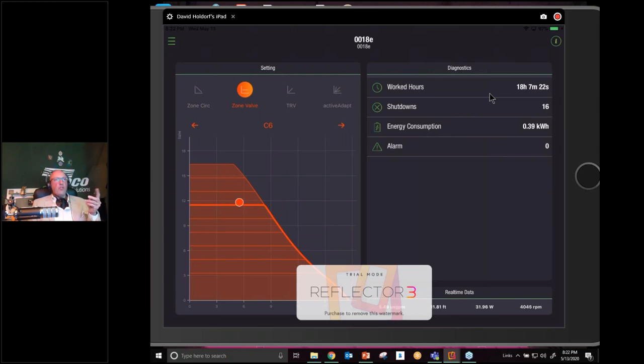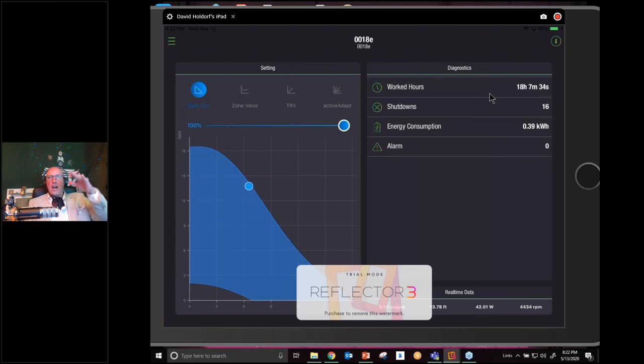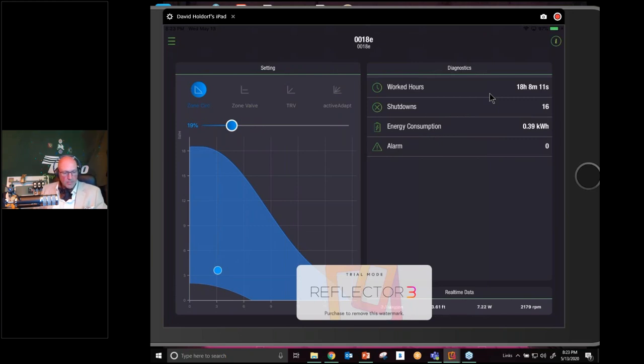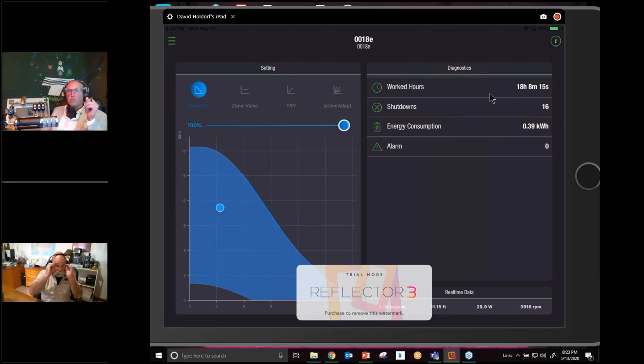One of the questions was, why did the dot flash red briefly? It was probably under the zone circ when I was speeding it up and down and changing it quickly. That just means it was finding which curve to operate on. So it just took a while to learn. I just went from 100% down to 37, and the dot was hunting all over the screen. Usually when I start low and go to high, I see it go to red, or when I've got low flow on the system. Right now I've got all three zones open. I find it's on the low flow when I get down to that 10% range and then crank it up, and it's closer to the left side of the curve compared to the right side. It's just the software trying to find where it is at the moment, and it kind of goes out of the curve.